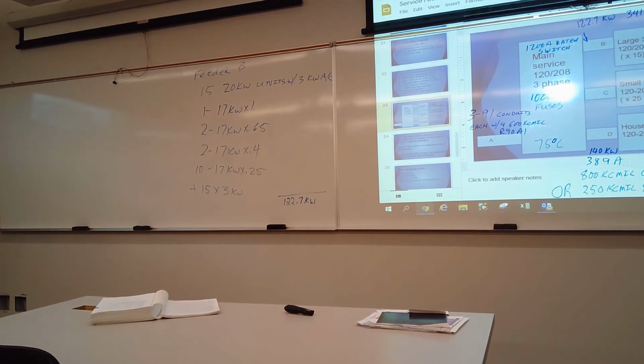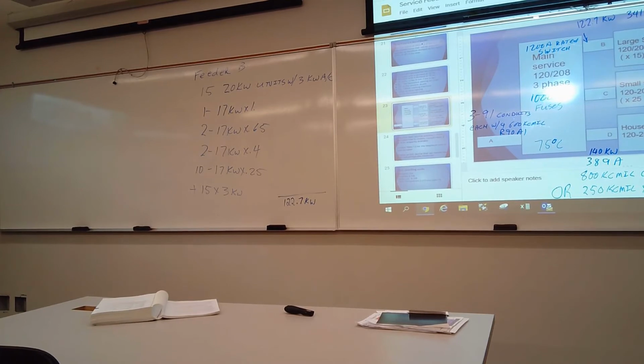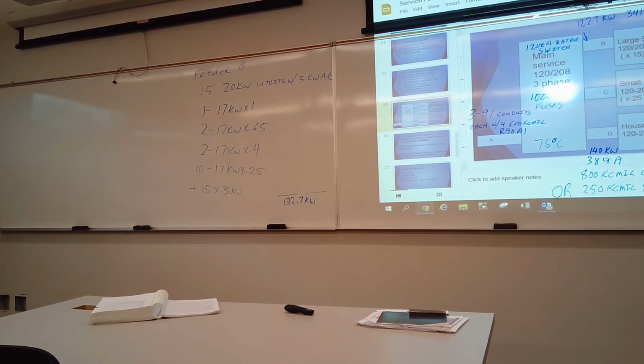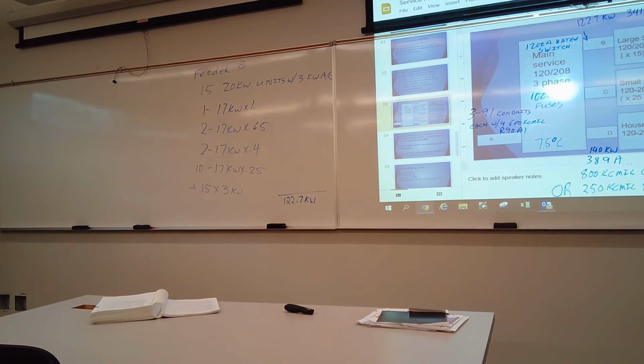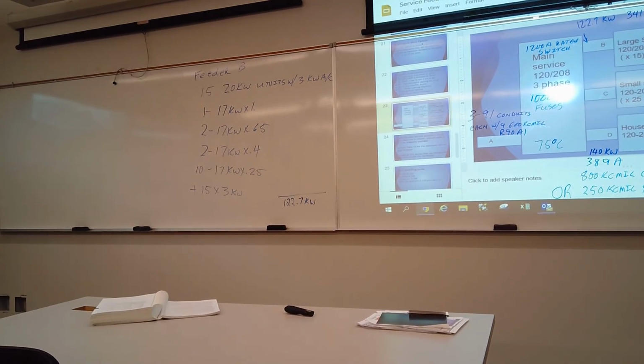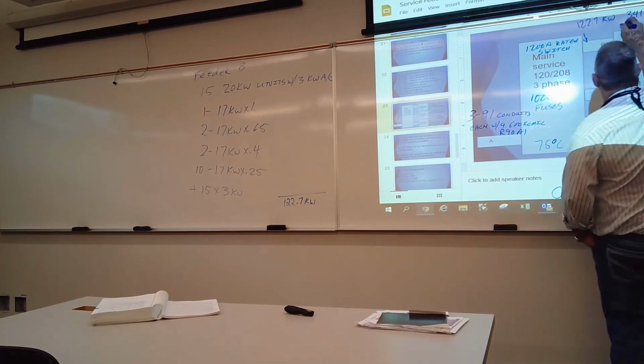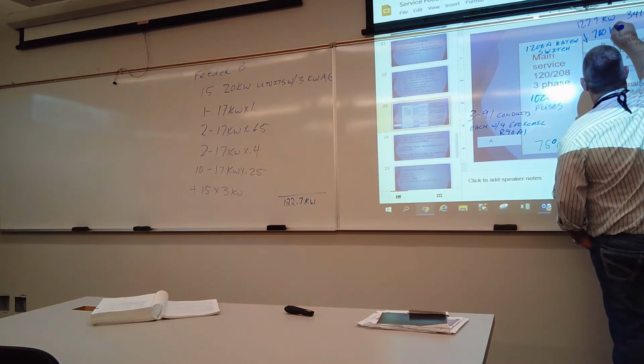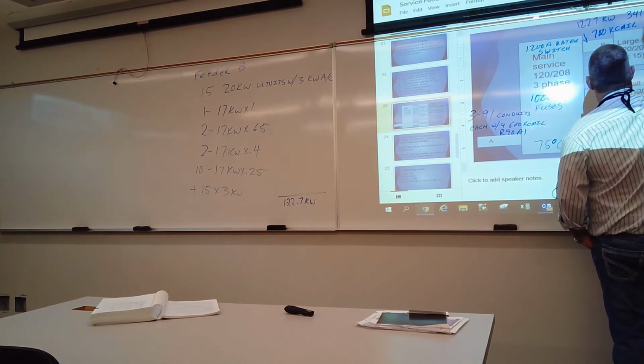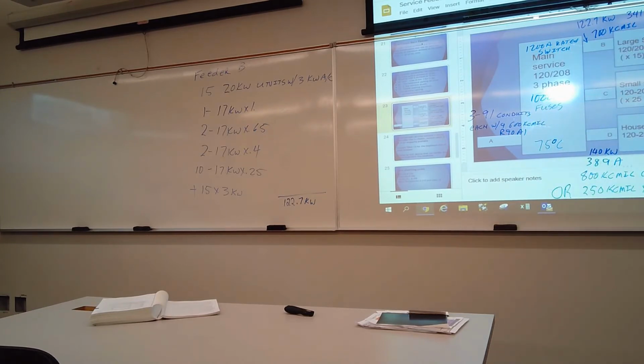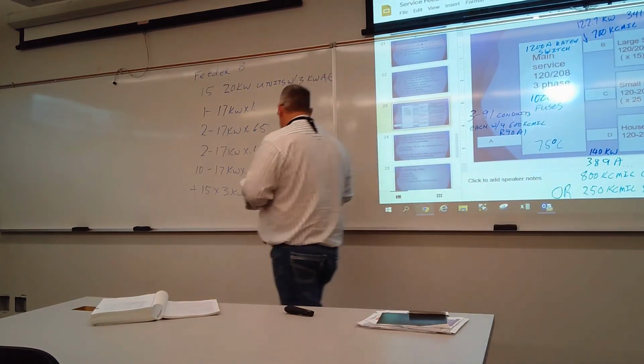So for 341 amps at 75 degrees, no, we should be 750s, right? I think 700s are quite good. So we need 700 kcmil conductors. There's going to be 4 of them. You can go to table 6 and find the conduit size. You guys are capable of that, I'm sure.